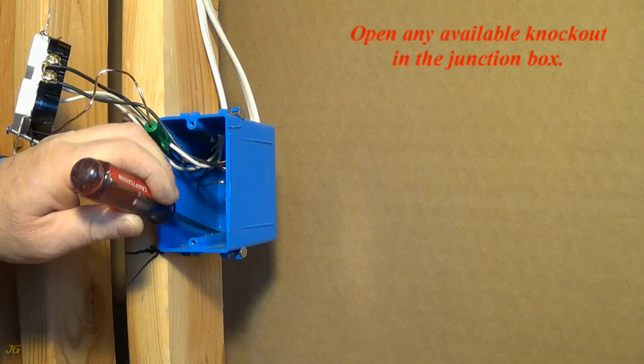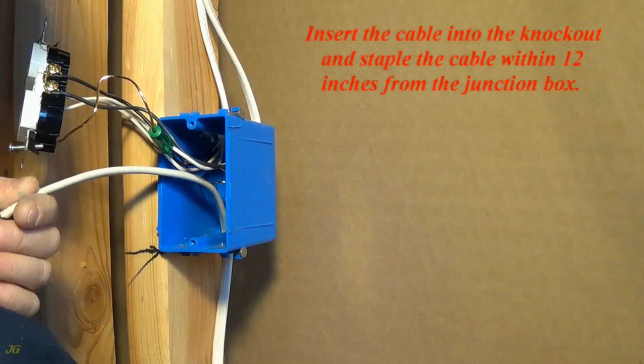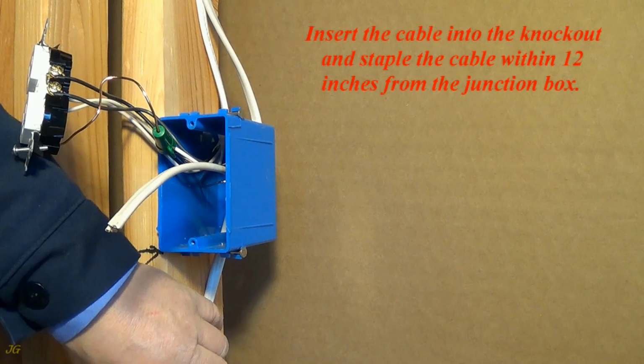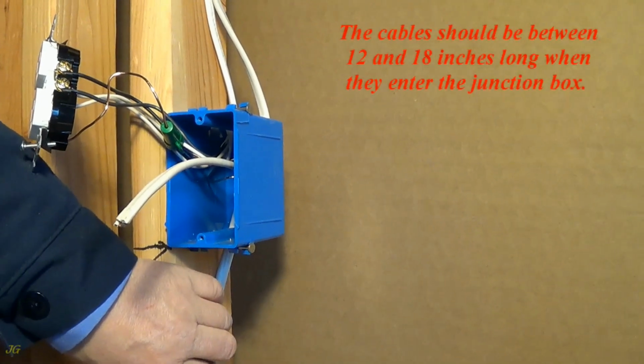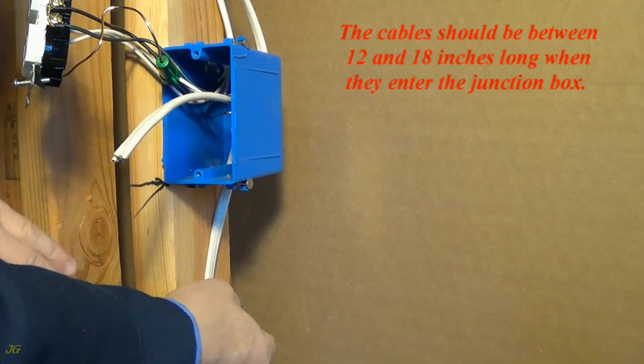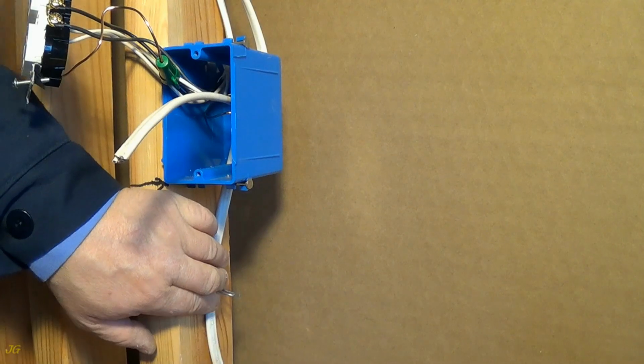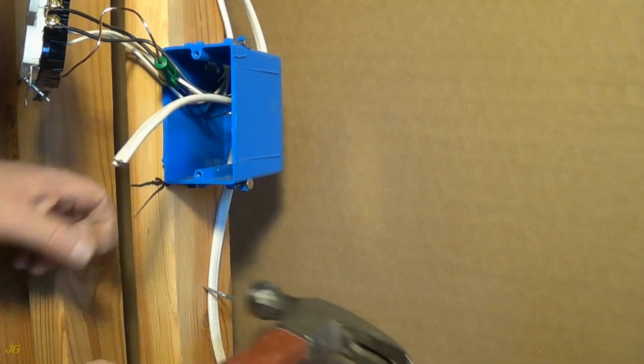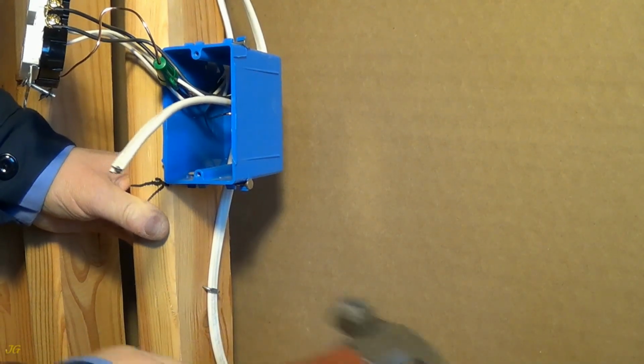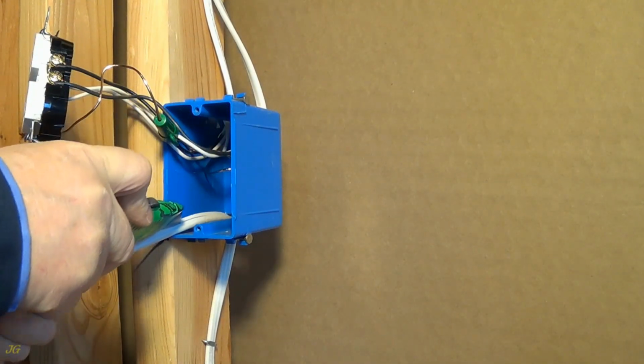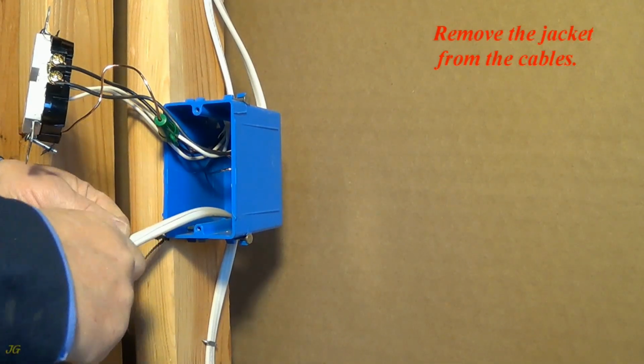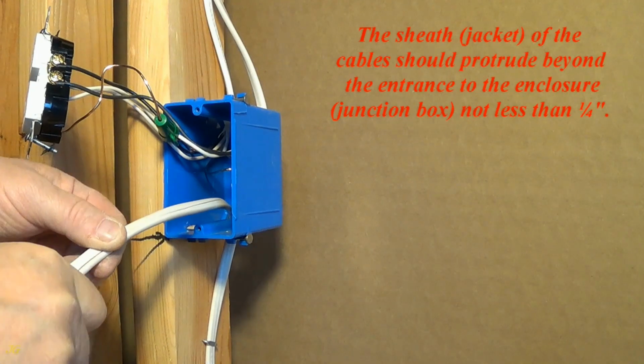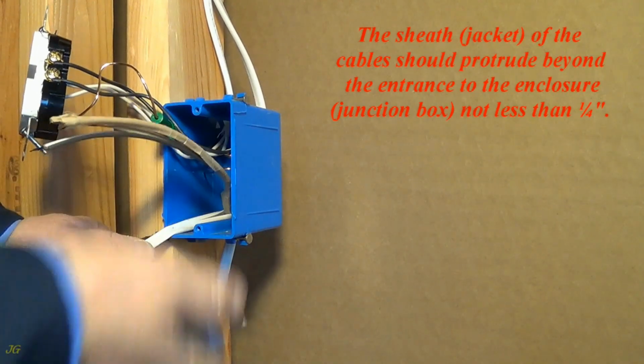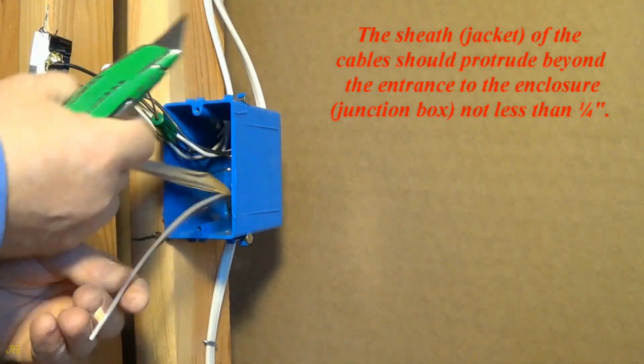Open any available knockout in the junction box. Insert the cable into the knockout and staple the cable within 12 inches from the junction box. The cables should be between 12 and 18 inches long when they enter the junction box. Remove the jacket from the cables. The sheath, jacket, of the cables should protrude beyond the entrance to the enclosure, junction box, not less than 1/4 inch.